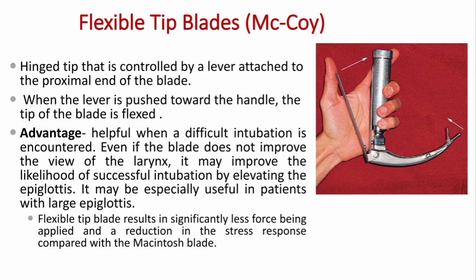Another type of blade is the flexible tip blade, also known as the McCoy blade. It has a hinged tip controlled by a lever attached to the proximal end of the blade; when the lever is pushed toward the handle, the tip of the blade is flexed. This is helpful when a difficult intubation is encountered — even if the blade does not improve the view of the larynx, it may improve the likelihood of successful intubation by elevating the epiglottis. It may be especially useful in patients with a large epiglottis. The flexible tip blade results in significantly less force being applied and a reduction in the stress response compared with the Macintosh blade.